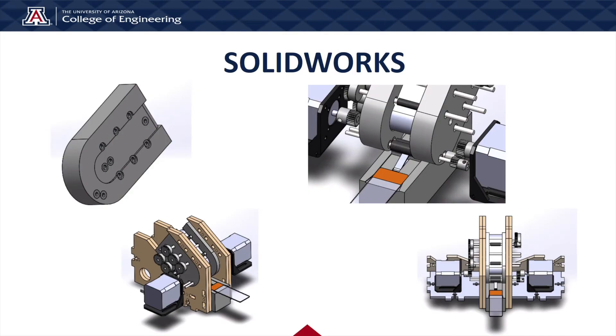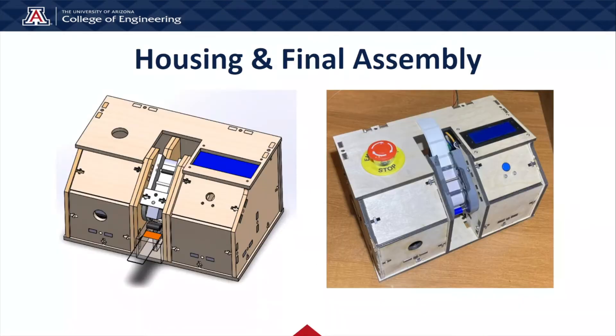This design was made almost entirely in SolidWorks. The channel side piece features an overhang of about one to two millimeters, which restricts the border on the label backing tape. The secondary rollers pull the label off of the backing paper and guide it onto the slide in a consistent location. Two stepper motors are used: one driving the primary rollers and conveyor belt, and another driving the secondary rollers to apply the label directly onto the slide. The label applicator subassembly is mounted at an angle within our system, such that the user can insert a slide horizontally. This allows easier use and prevents any tissue sample from falling off of the slide.